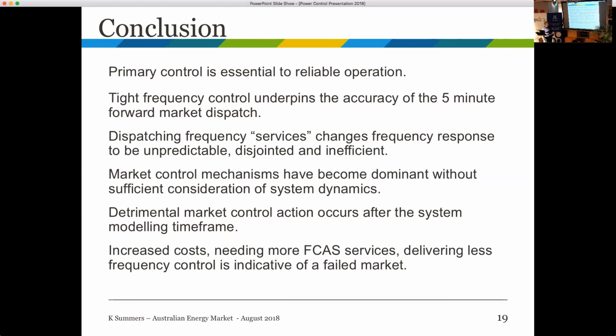There's detrimental market control action, and it can occur after the system modelling time frame. So when we model a system and we look at it, it's usually about 10 seconds to 15 seconds. And the market systems can kick in after that period. And we're seeing increased costs. People are crying out for more FCAS services, but the more FCAS service we deliver, the less frequency control we have. This is indicative of a failed market. We need to get the fundamentals right. And I've got a couple of references there for you. There you go.